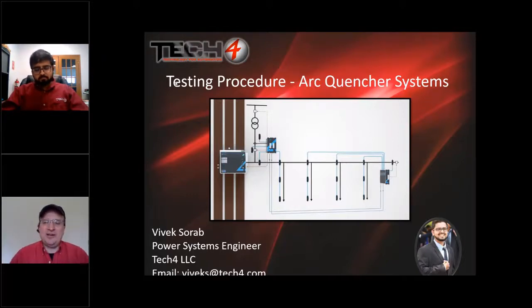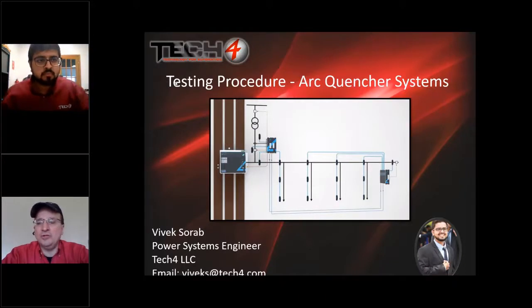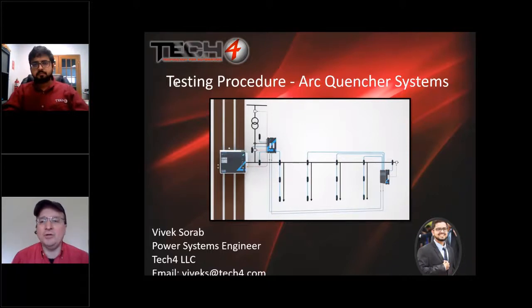And the resettable nature of this arc quencher solution is valuable for 2 reasons. One, if you ever have an arc flash event and you're in any type of critical power application, the ability to get your system rapidly back online once you remediate the cause of the fault event could be important to the operation. So that's the first reason why resettability is important.